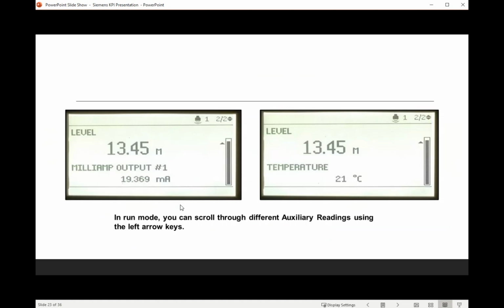And if you hit the left arrow key when you're on this screen, you can cycle through all of the different auxiliary readings. So you can see your milliamp output at the same time as your level. You can also see your distance measurements. So what this allows, it allows for an easy way to troubleshoot and basically confirm that the Hydroranger is working properly.